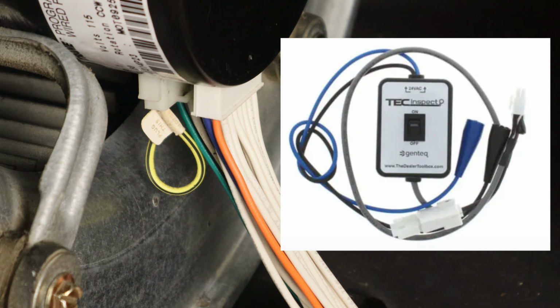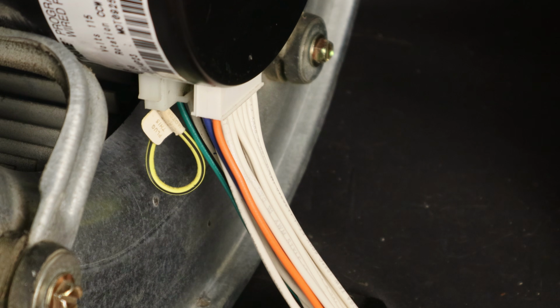And basically what I'm doing here is I'm using the 120 volts directly from the control board to run the motor. And the ECM tester is just giving the module the signal to run. If the motor does run at that point, then the problem may be with the harness itself or the control board. If it doesn't run, then the problem is likely with the module or the motor. Now, in the beginning of the video, I mentioned there is a jumper trick you can use if you don't have an ECM tester, and I'll show you that next.